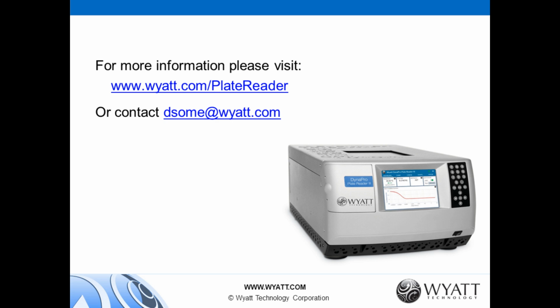Okay, perfect. Our next question: what is the concentration range that can be used for the plate? First of all, the concentration range depends on the molecular weight of the protein, but let's focus on IgGs. For IgGs, we have a minimum sensitivity for making a good measurement of size at 12.5 micrograms per milliliter. We have a minimum concentration for good measurement of molecular weight, which is about 0.4 milligrams per milliliter. And then you can keep going.